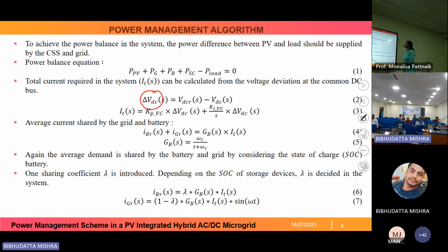power management algorithm. So here we can see that by subtracting the actual DC bus voltage from the reference DC bus voltage, we can calculate the deviation at the DC bus voltage. Then by using a voltage controller, which is nothing but a simple PI controller, we can calculate the total current in the system. As we know, the battery can take the average current required in the system and the supercapacitor can take the transient current in the system.